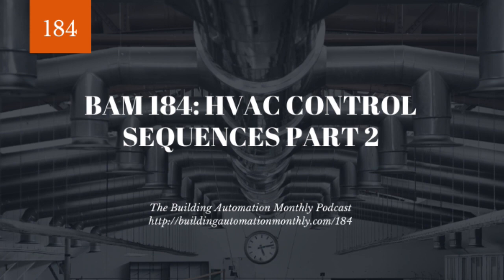Where'd it go? Single zone rooftop unit. And in this, it says a programmable thermostat controls the operation of the rooftop unit. Wow, that's amazing. Desired occupied and unoccupied heating and cooling set points are programmed via the thermostat. Okay, folks, if you're having a mental lock on this and you're like, it's not using a thermostat, it's using controls, okay, well, I'm going to help you out here. Replace programmable thermostat with controls. There you go. Thank you. All right. It's early in the morning. I'm a little sarcastic.